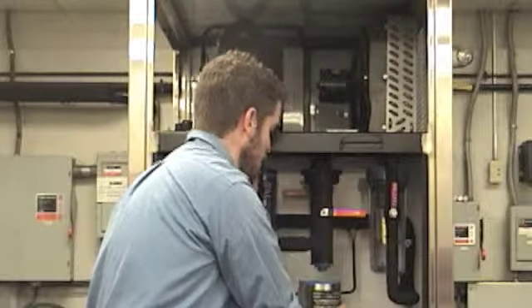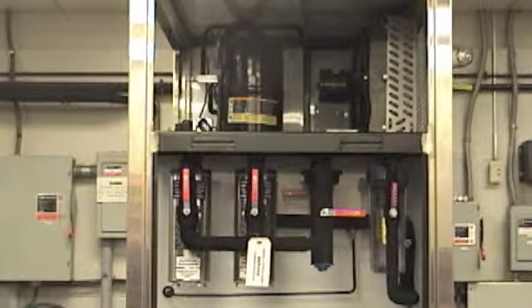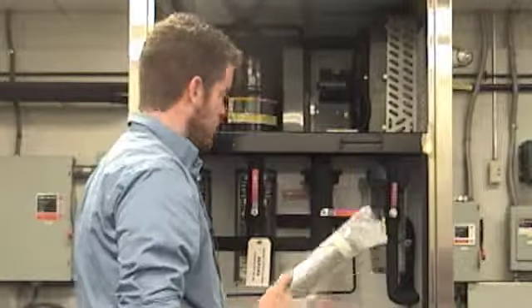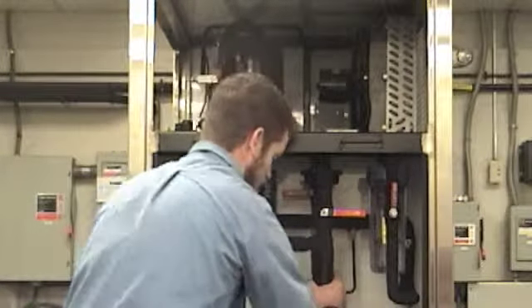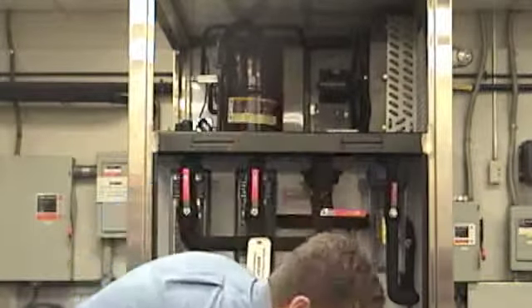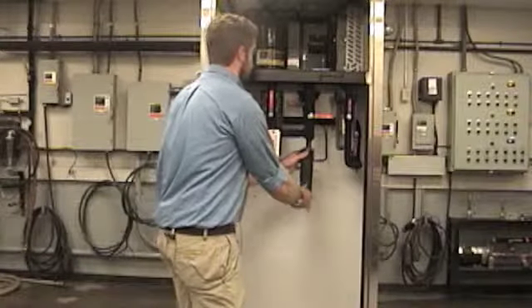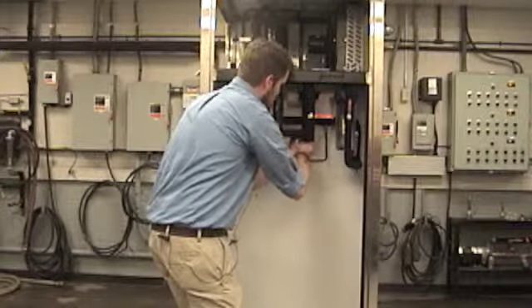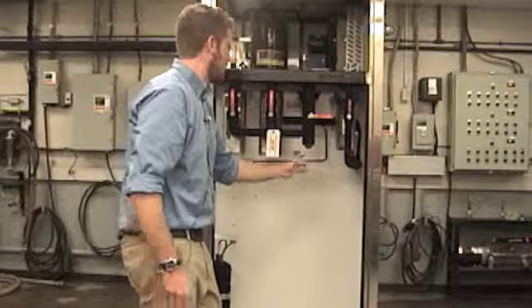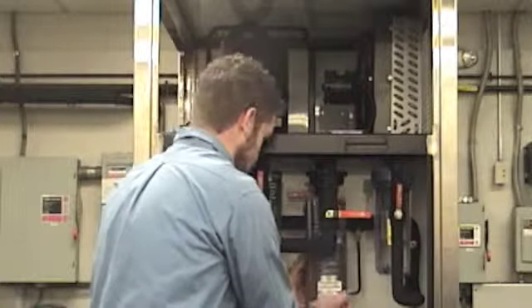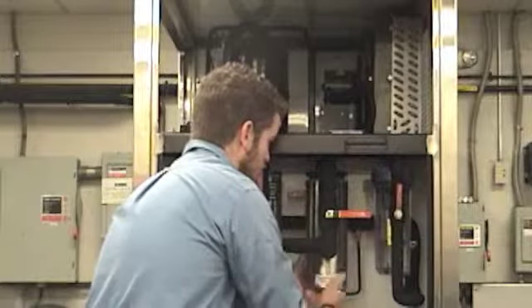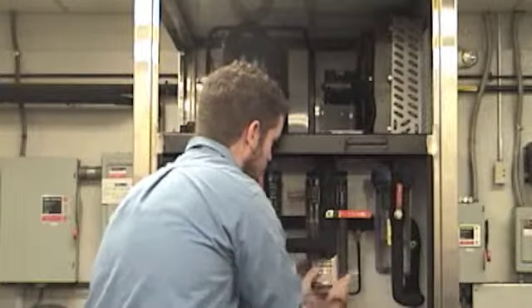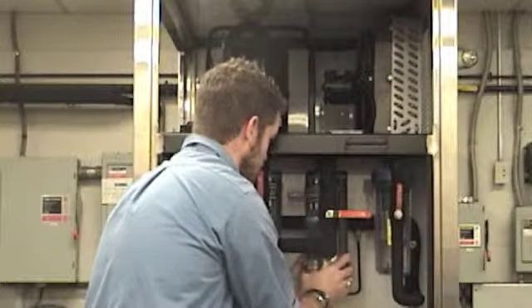You will have a little bit of water in it, but it'll be displaced by the filter element, the old filter element. So you'll take off the old element, unpack a new one, and slide it onto the standpipe. Make sure that it gets all the way on and is covering all of the holes on the standpipe. After you put the new element on, you can replace the bottom of the housing, and really these just need to be hand tight.